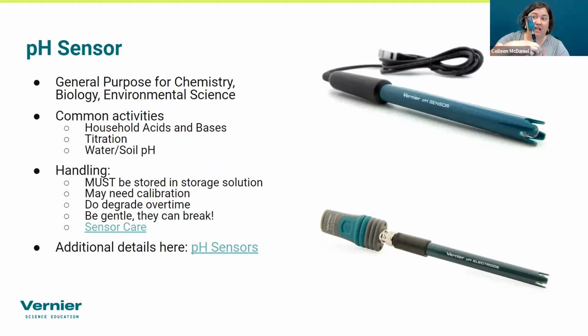The other thing to be careful with is that there's an exposed glass bulb on the tip of the sensor. You can kind of see it in the picture on the website or on the slide here. Since it's exposed glass, it can break, so you want to forewarn your students to be very careful with it, because even gently tapping it against a beaker can cause the bulb to break. If it breaks, there's no repair we can do for it, so sadly it would mean replacing the sensor.